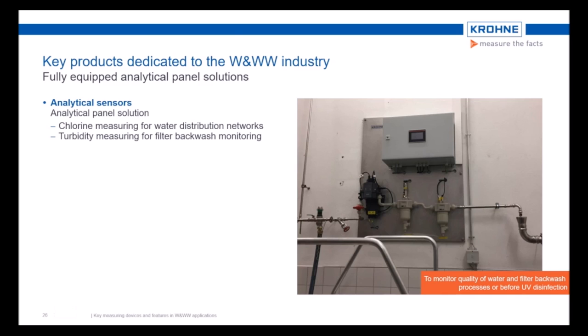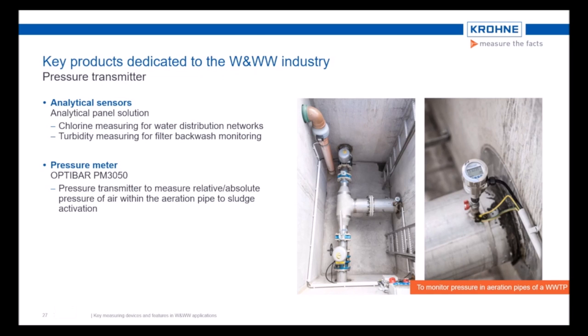in the previous slide. Next application to be presented is a pressure application in an aeration tank. Pressure must be measured in the aeration pipe for aeration tanks. If the pressure rises, this could be an indication of clogging aerators or wear of the diaphragm. High pressure also leads to higher power consumption, which is one of the most important parameters to be adjusted to make such a plant more efficient.